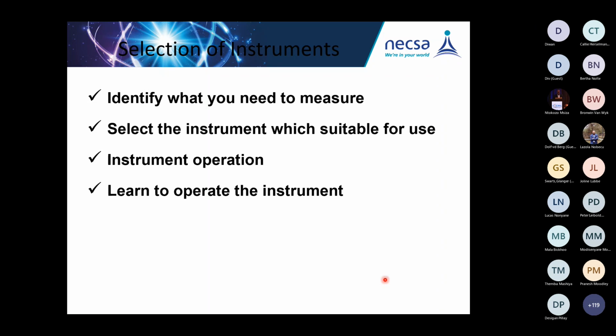There are certain instruments that can measure alpha and beta. There are other instruments that can measure gamma. Not all instruments can be 2-in-1, but I'll show you an instrument which is 2-in-1, which can measure alpha, beta, gamma, and also an instrument which can measure alpha and beta for surface contamination. You need to select the instrument which suits the area. Just as a typical example, if you don't handle uranium but you buy an instrument which can also measure uranium, that will be like a bonus, but it won't help you measure the nuclides which are actually available, which are the area of concern.